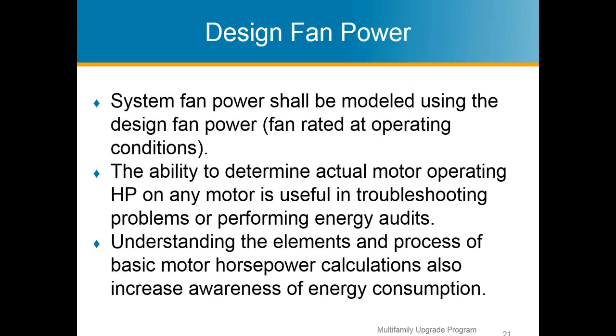So just to recap on the system fan power, we model using design power. So that's your fan rated at operating conditions. It's very important to know what actual motor operating horsepower is. It's useful information for troubleshooting problems and doing either modeling or performing energy audits. Fan energy is a big component of energy consumption. Understanding the elements and process of basic motor horsepower calculations also increases the awareness of energy consumption to yourself, to your client, to your tenants, to everybody that's reaping the benefit of these systems.